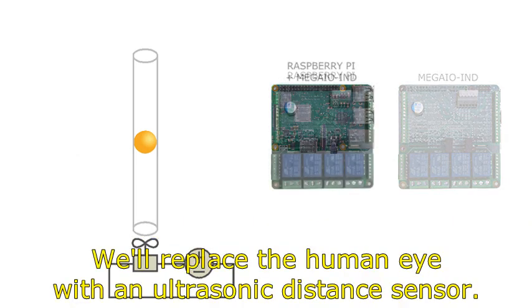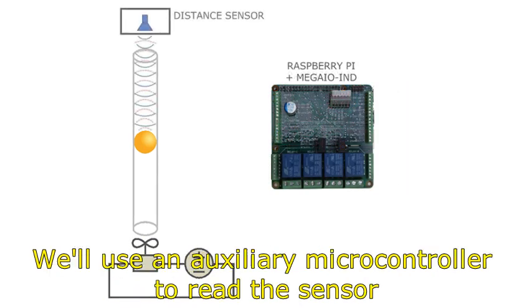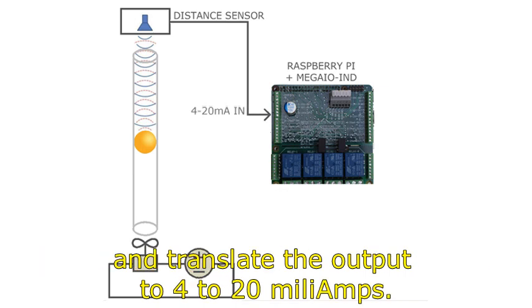We'll replace the human eye with an ultrasonic distance sensor. We'll use an auxiliary microcontroller to read the sensor and translate the output to 4 to 20 milliamps.